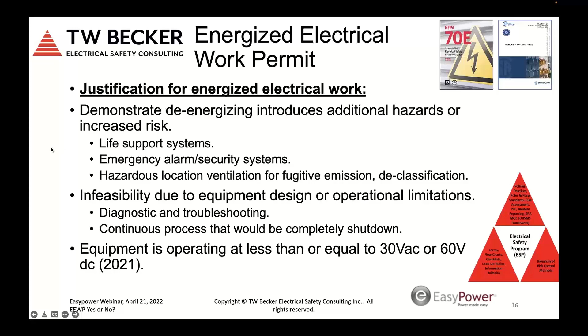And what we really want to do then is look at the exemptions that are currently in 70E and Z462. So if we look at the exemptions right now, the first one is testing, troubleshooting, or voltage or current measurements. Well, really, let's just change the wording to say any use of a test instrument doesn't require a permit because of equipment design. How do we do diagnostics if we can't have voltage present? We need voltage present, right, to get different measurements.